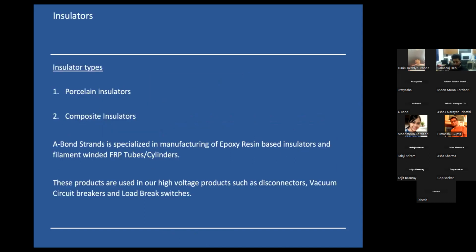Coming to insulators, the main two insulators used in the electrical industry are porcelain insulators and composite insulators. We specialize exclusively in manufacturing epoxy resin-based insulators and filament-wound FRP tubes. These products have certain advantages over porcelain insulators: they are lighter in weight and have higher strength. In most indoor applications, epoxy resin insulators are the go-to product. As a case of forward integration, most of these insulators are used in our other products like disconnectors, circuit breakers, and load break switches.